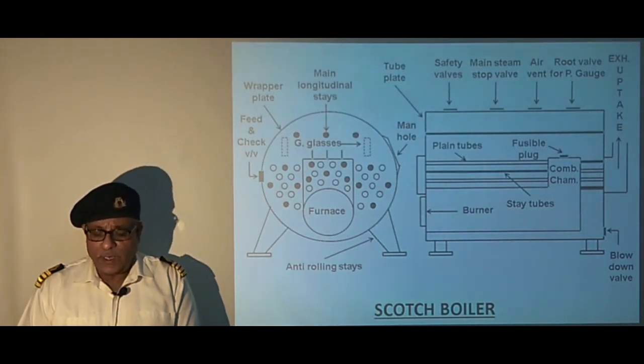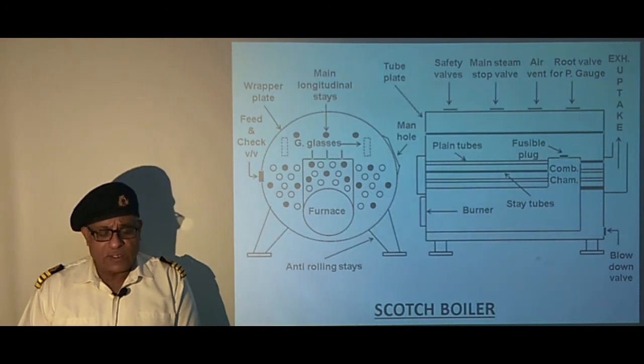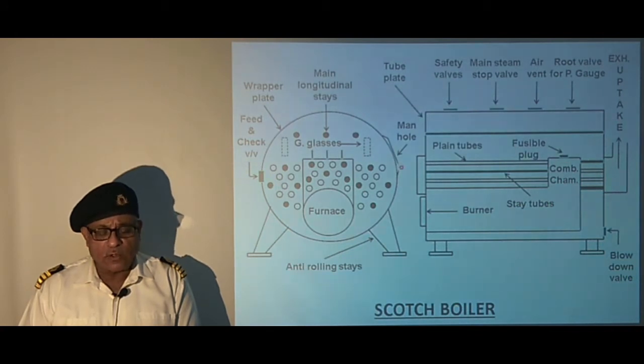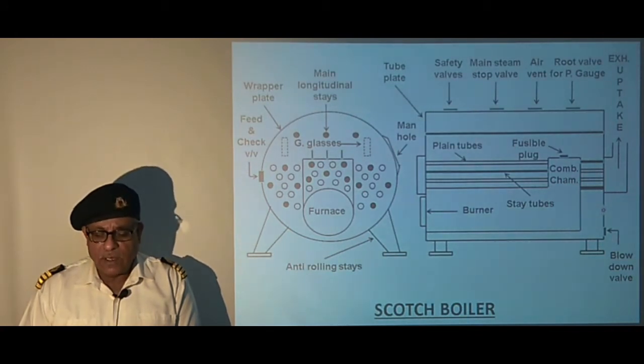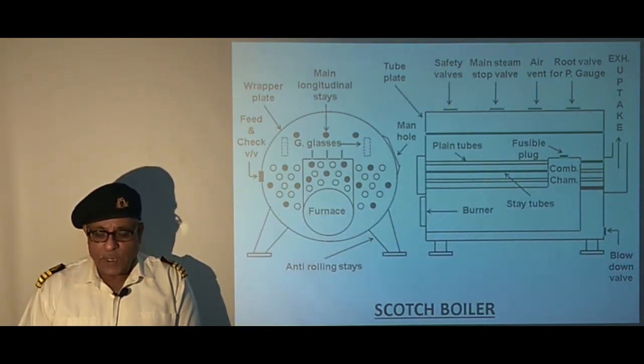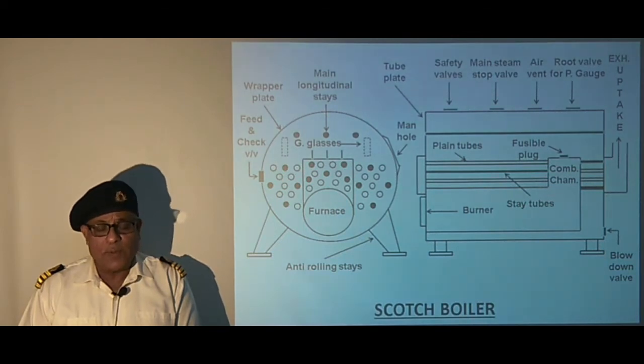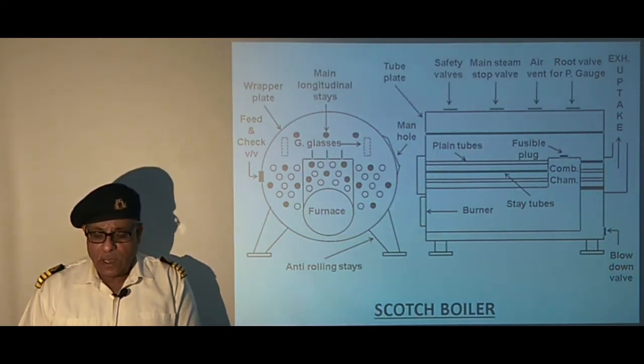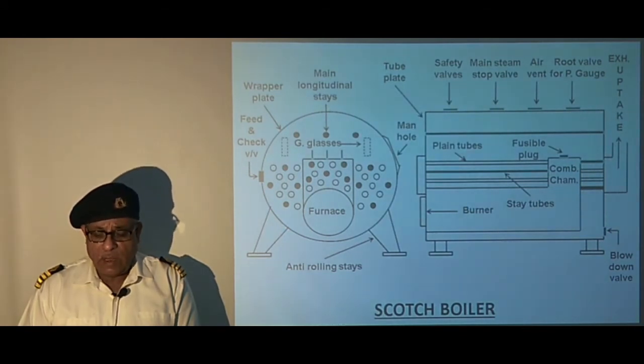Two manhole openings are usually provided — one on the wrapper plating and the other on the rear side of the boiler tube plate. These openings are compensated to restore plate strength, and the manholes on the wrapper plating should have their minor axis parallel to the boiler axis.